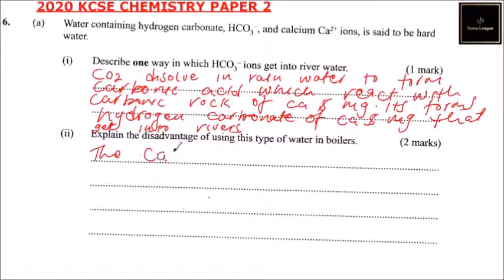Roman number 2, explain the disadvantage of using this type of water in boilers. So the disadvantage is that the calcium hydrogen carbonate and magnesium hydrogen carbonate decompose, forming scale, which lines the walls of the boiler, causing poor thermal conductivity.